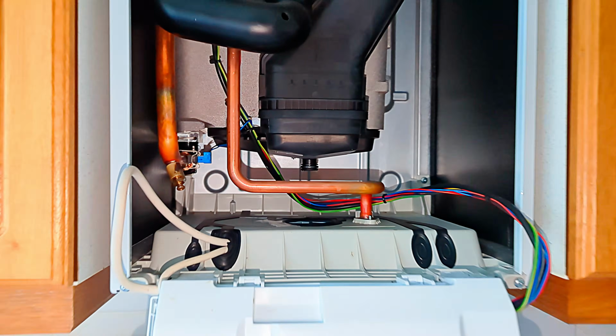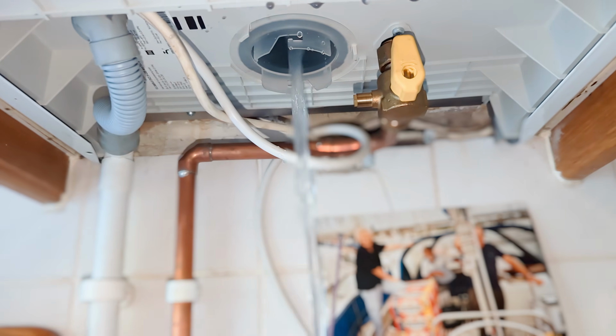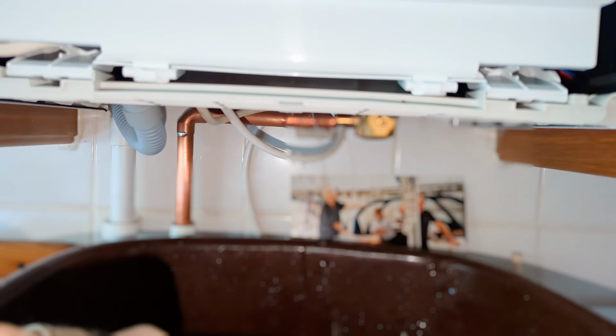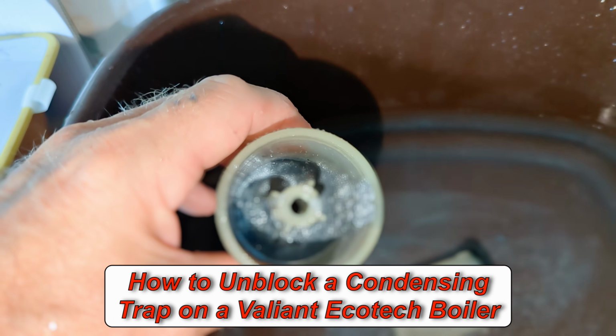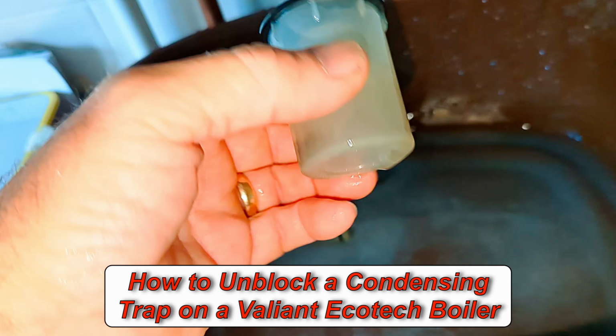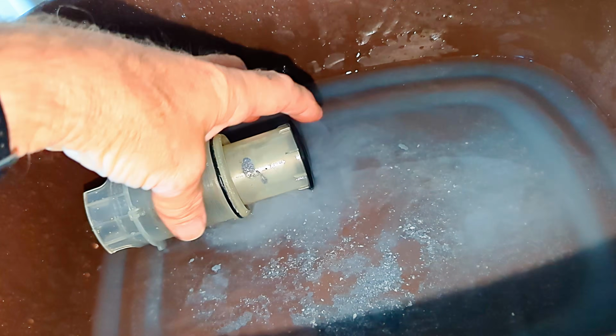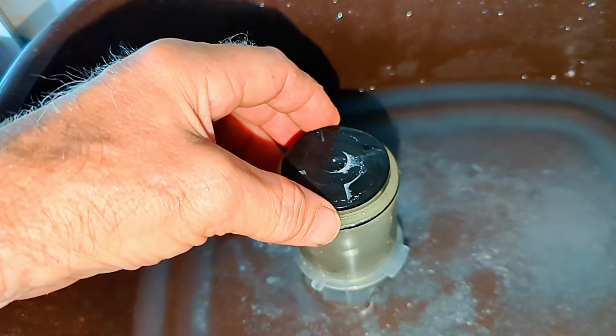Now you just saw me remove the trap and you saw all that water come running out of the bottom of the heat exchanger. Now that's not exactly what happened. I was just showing you that for presentation purposes. So let's just run through exactly what I had to do to clear the blockage. Now firstly, you don't need to remove the cover of the boiler to check to see if you've got a blockage and clear it if you need to.